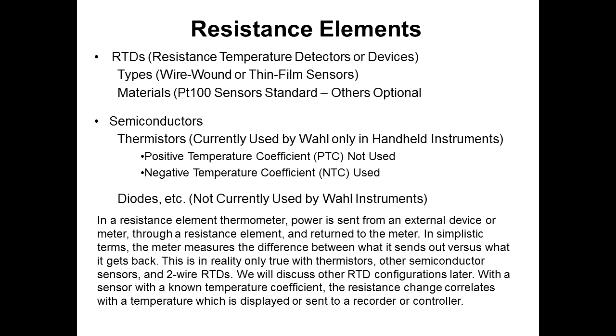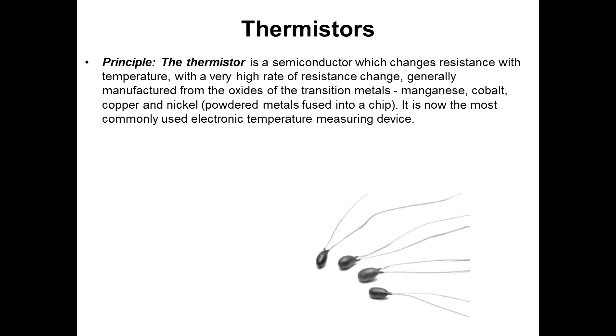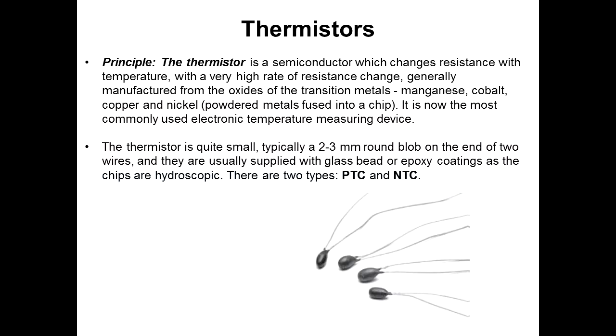So you have a sensor with a known temperature coefficient. The resistance change correlates with the temperature, which is displayed or sent to a recorder or controller. A thermistor is a semiconductor which changes resistance with temperature, generally at a very high rate of resistance change. This is manufactured from oxides of transition metals, manganese, cobalt, copper, and nickel, powdered metals fused into a chip. It's the most commonly used electronic temperature sensor out there now. All of your fever thermometers, your air conditioning controls, thermostats, things like that use thermistor sensors. They're very, very small, typically 2 to 3 millimeters, a round blob with 2 wires coming out. They're coated with glass or epoxy.